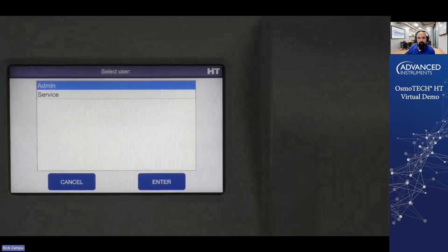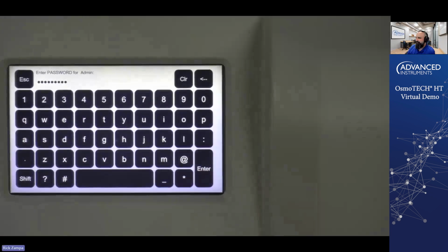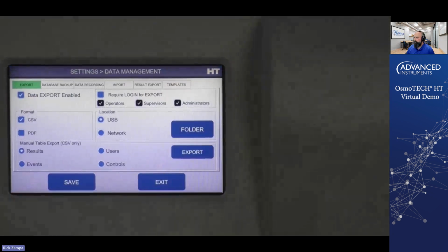Now we want to talk about how we're going to manage our data. One thing that's important to understand is that the instrument, now we start talking and forget to log in. The instrument for the audit trail and the results database has unlimited data storage, meaning that for the life of the instrument, you'll never fill up the memory in the system for your results database or your audit trail. It's also unlimited storage for your users and for your controls as well. However, these can be deleted if you want to. The audit trail and the results database cannot be deleted, cannot be modified, cannot be changed. You can't do anything to them. You can just export them off of the system.